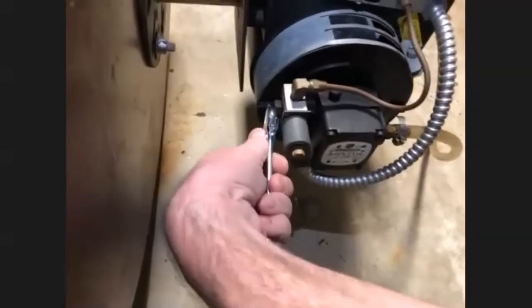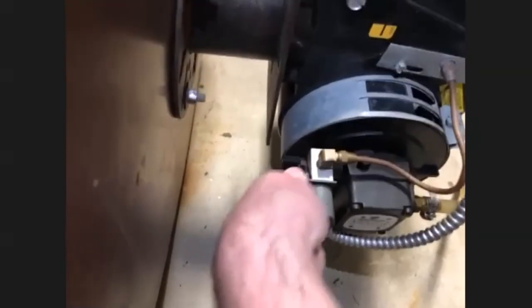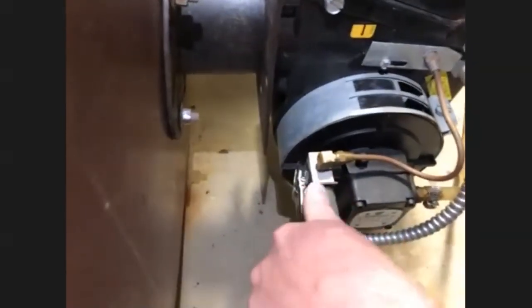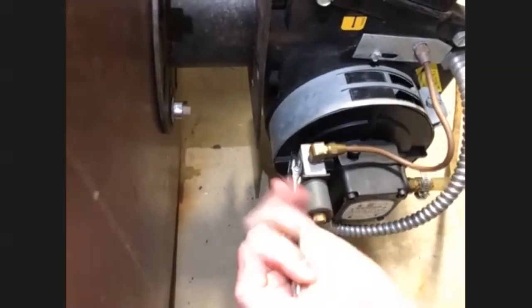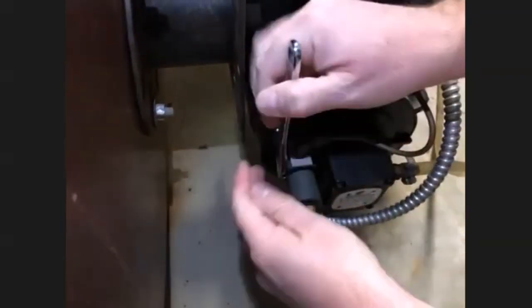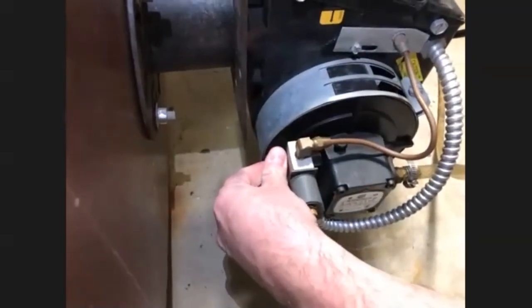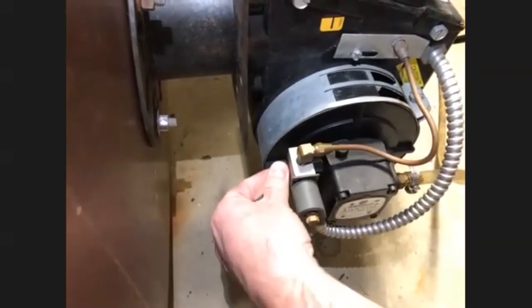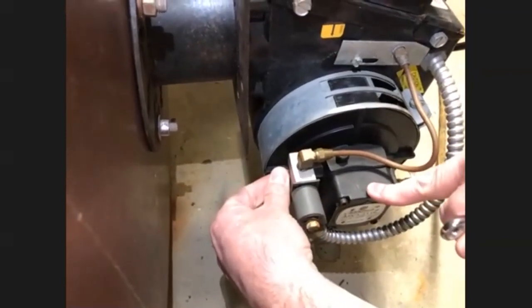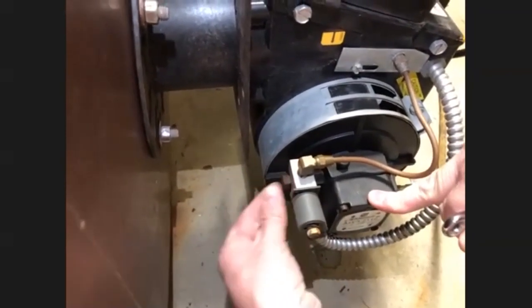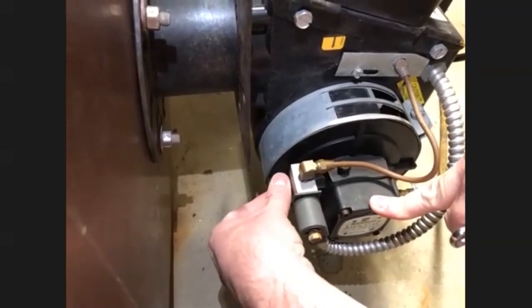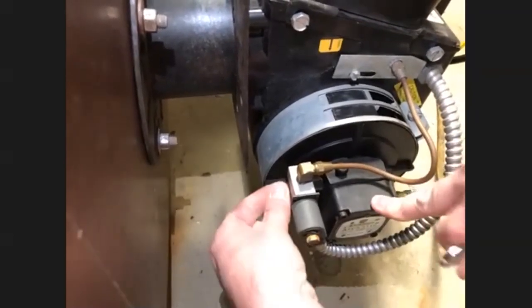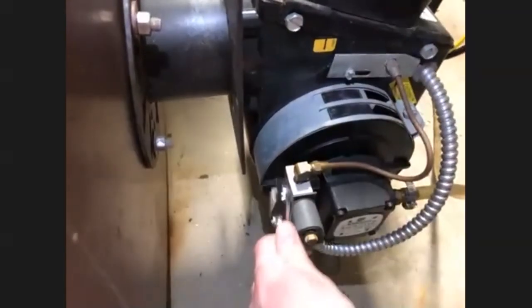You have your pump, you have your fuel valve right here, solenoid valve. So what you want to do is when you operate, you want to loosen this nut as it's trying to operate. When you loosen that, if fuel comes out, then you know your pump is operating properly. So again, you loosen this nut here, and if any fuel comes out while it's trying to operate, then the fuel pump is working fine. So you can tighten that back down.